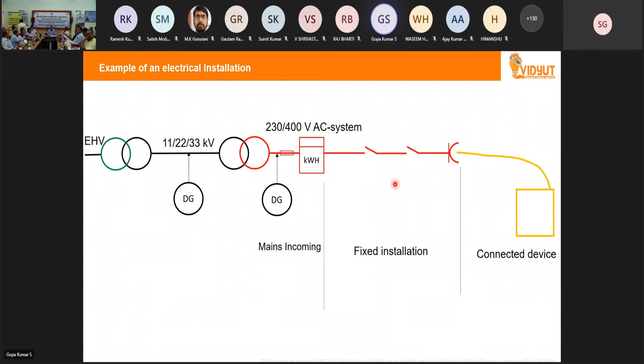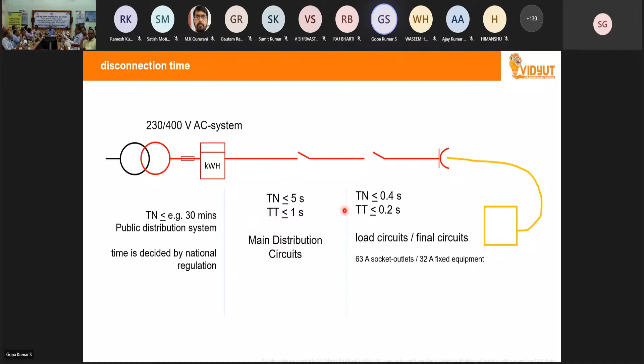Now, inside the low voltage system, the first subject of safety is achieved by protective equipotential bonding and automatic disconnection of supply. What it means is, from your meter, from your mains incoming up to the last socket, there is a defined disconnection time of the circuit in case of a fault. For example, for a TT system, 0.2 seconds for the final circuit. And for ensuring this disconnection, we are also supposed to make a safety measure called protective equipotential bonding.